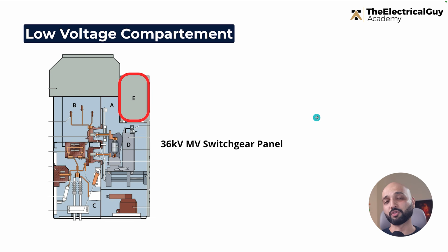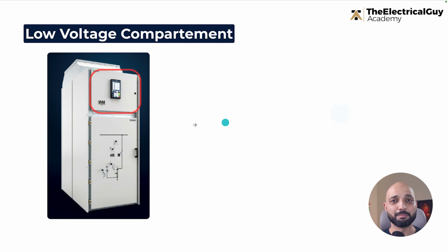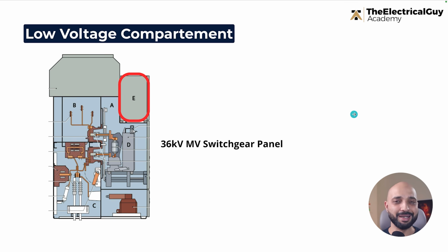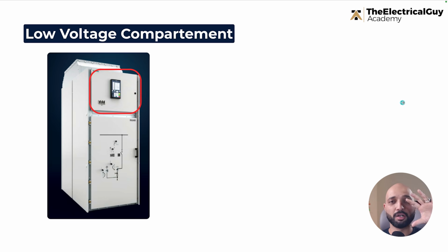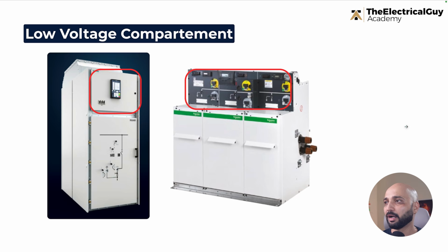Clear? Now the next question comes: where is this low voltage compartment or low voltage box placed inside the switchgear? Now there are multiple locations. Most commonly, if you're looking at the low voltage switchgear or the medium voltage switchgear, you will find them located on top of the switchgear, where all the indications and relays are accessible to the maintenance staff. One example you can see on your screen. On the ring main units also they will be there. So you can see on top of this ring main unit, the complete low voltage devices, compartment and indications are provided.